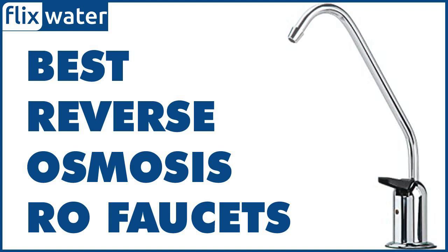Plumbing codes. The other major setback of non-air gap RO faucets is that they are often considered non-compliant with most local plumbing codes, since many of them require RO systems to be installed with air gap faucets. Furthermore, while air gap faucets can work with both a non-air gap and air gap RO system, non-air gap faucets can only work with non-air gap systems, which kind of limits your ability to customize your RO system in case your building code requires an air gap system.